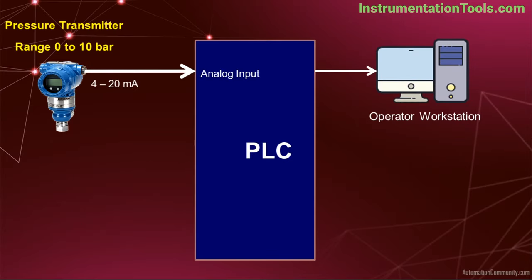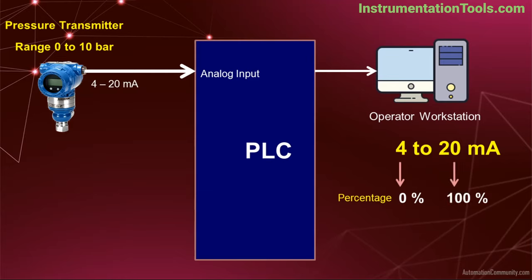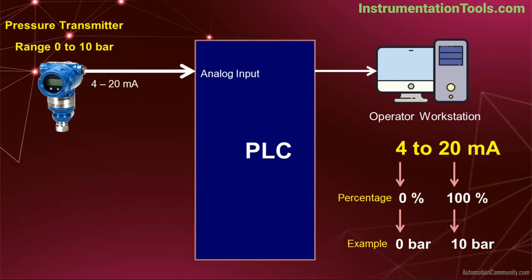Now let's discuss a pressure transmitter with 4 to 20 mA current output. Assume the pressure transmitter is configured with a range of 0 to 10 bar. 4 mA represents the 0% process variable and 20 mA represents the 100% process variable. In this example, 0% of the process variable is 0 bar and 100% of the process variable is 10 bar. The PLC is also programmed with the same range of 0 to 10 bar, and calculates the received mA into the equivalent pressure and displays it to the operator.